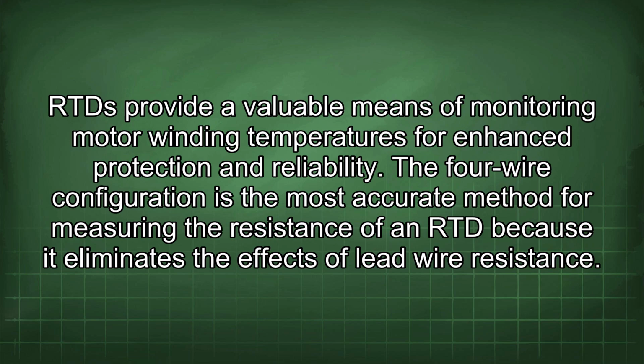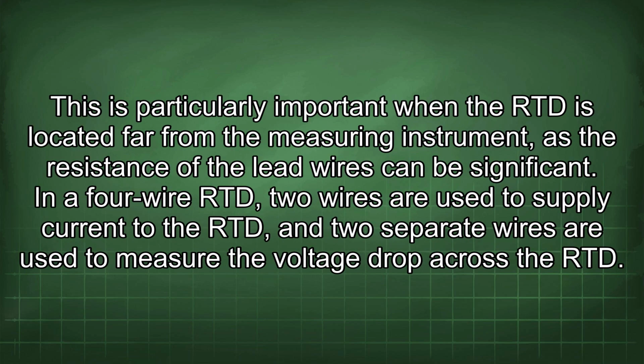The 4-wire configuration is the most accurate method for measuring the resistance of an RTD because it eliminates the effects of lead wire resistance. This is particularly important when the RTD is located far from the measuring instrument, as the resistance of the lead wires can be significant. In a 4-wire RTD, 2 wires are used to supply current to the RTD, and 2 separate wires are used to measure the voltage drop across the RTD.